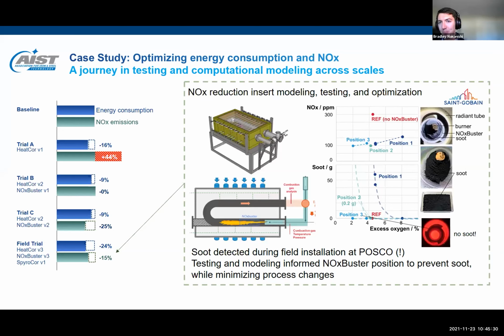Can you provide a better explanation for soot in the NOx Buster and how it was solved? Sure, maybe I'll share my screen to go back through that. One of the problems we encountered during the installation was that the NOx Buster positioning was installed in a variable arrangement. So we did some additional testing at SGR Paris, where we took a similar size radiant tube, burner setup and operating conditions. We placed the NOx Buster in the radiant tube and looked at different positioning effects, the burner, the air fuel ratio, and other conditions of the application to try to identify what might have been causing the soot formation that we observed during the field trial.